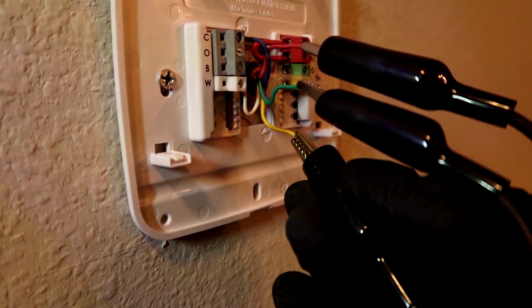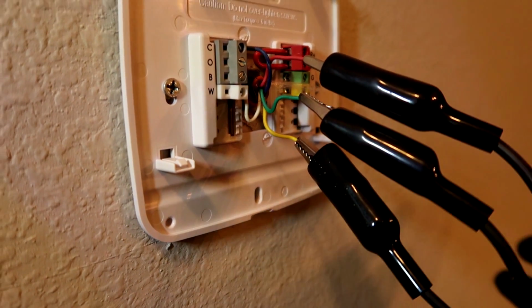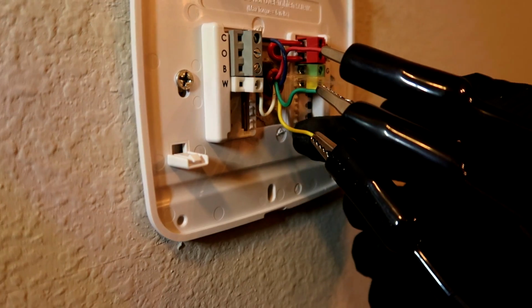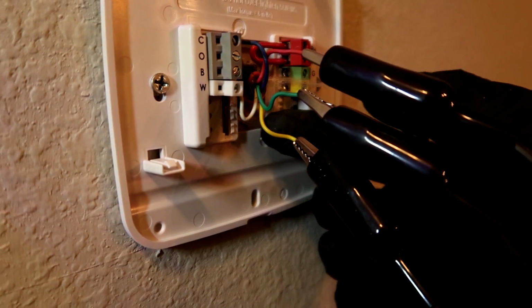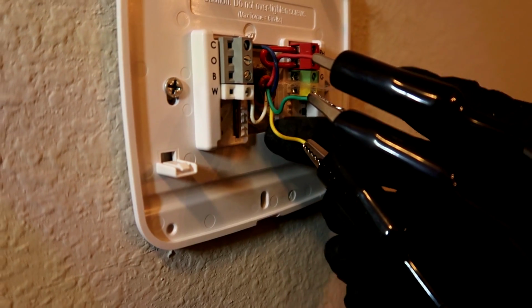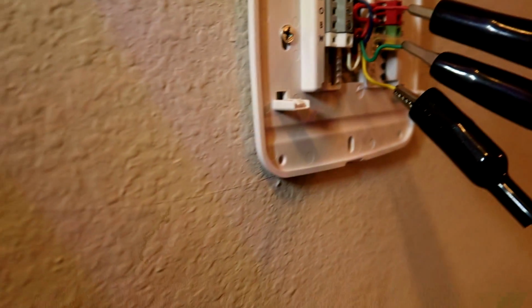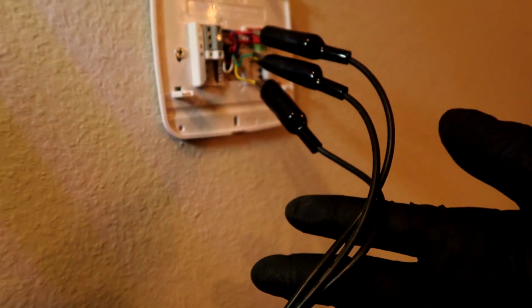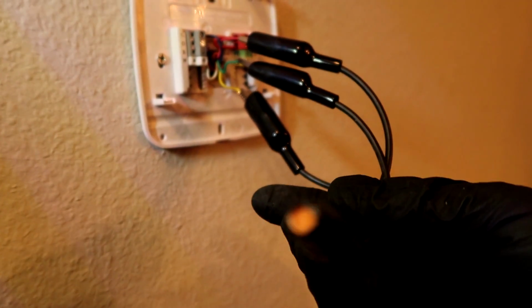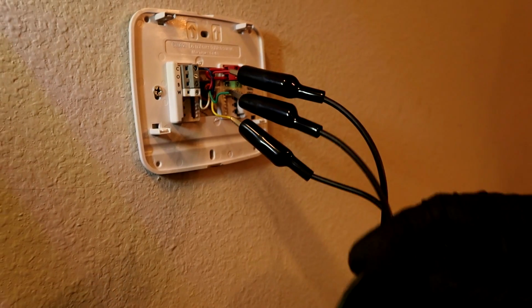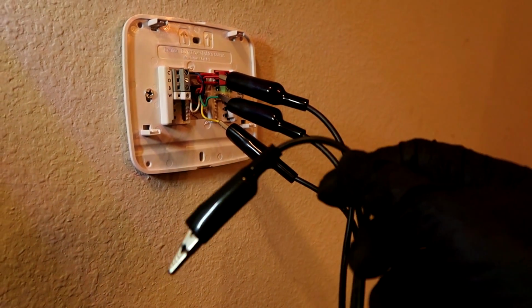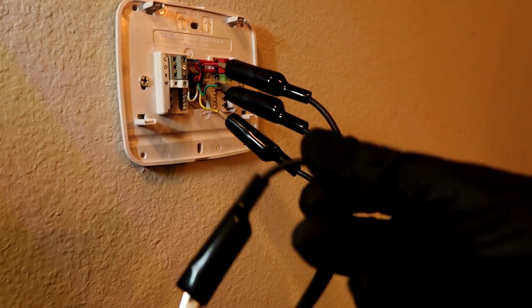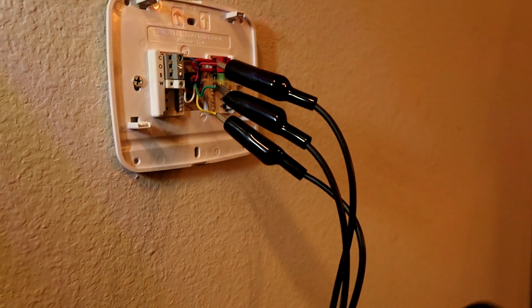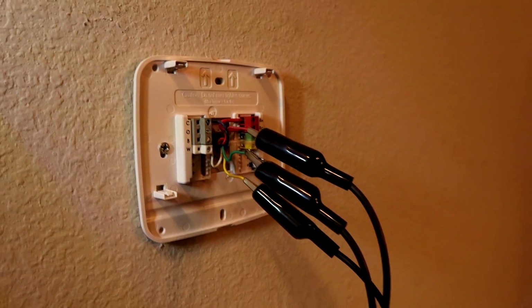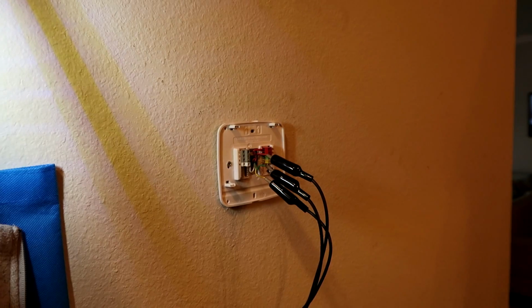So that'll get the indoor fan and the outdoor condenser to come on. If the fuse pops, then I know the problem is on this yellow wire, because that's the wire going out to the condenser. Probably a bad contactor or something. I just took a wire nut, some electrical tape, and cut the wires. Order these off Amazon. Again, I'll leave a link if you're interested in a nice jumper. Instead of just 2 wires, I got 4. So if you got a heat pump, you can throw the orange wire in there, but this is a straight cool, so no need for all that.